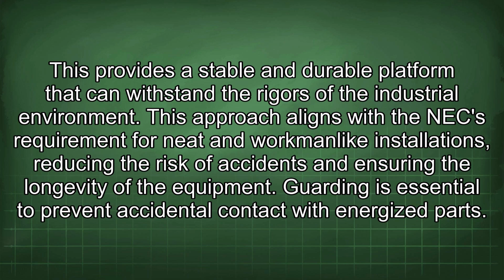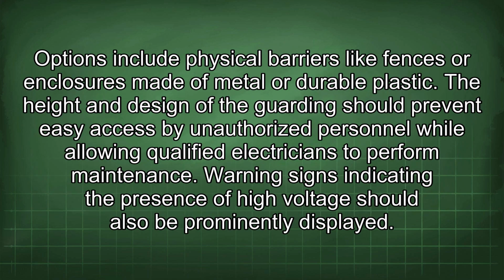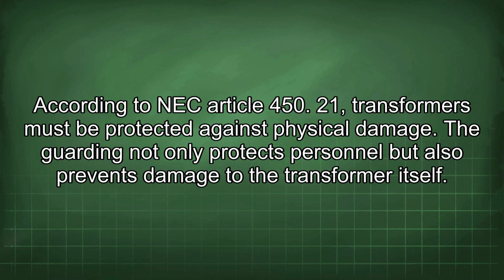Guarding is essential to prevent accidental contact with energized parts. Options include physical barriers like fences or enclosures made of metal or durable plastic. The height and design of the guarding should prevent easy access by unauthorized personnel while allowing qualified electricians to perform maintenance. Warning signs indicating the presence of high voltage should also be prominently displayed. According to NEC Article 450.21, transformers must be protected against physical damage. The guarding not only protects personnel but also prevents damage to the transformer itself.